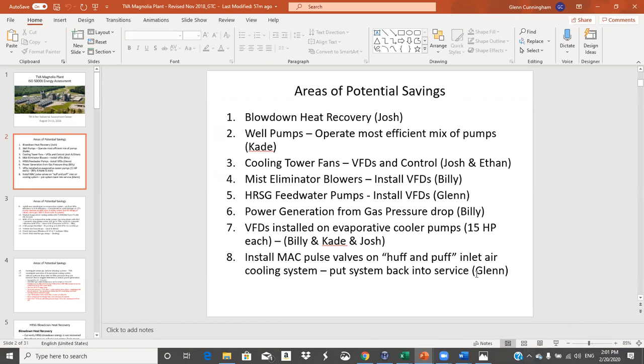Cooling tower fans. Okay. So each one of those towers has 5 fans. And in the old days, the old way of operating a cooling tower with 5 cells is, let's say it's cool outside and we don't need full capacity, we'll operate these 3 cells and turn these 2 fans off. So you're running 600 horsepower, and you've got 400 horsepower off, and you're at 60% capacity. The more energy efficient way is to put a variable frequency drive on each one of these that allows speed control and operate all 5 motors at 60%.